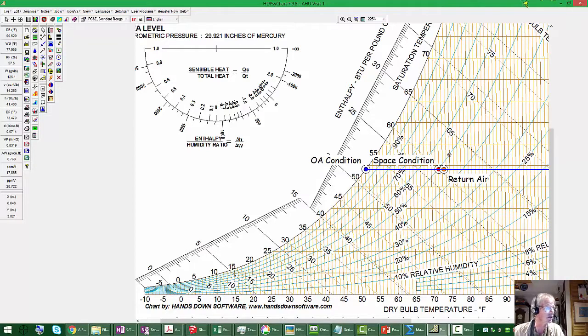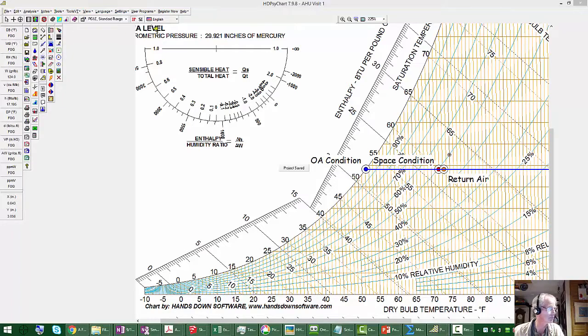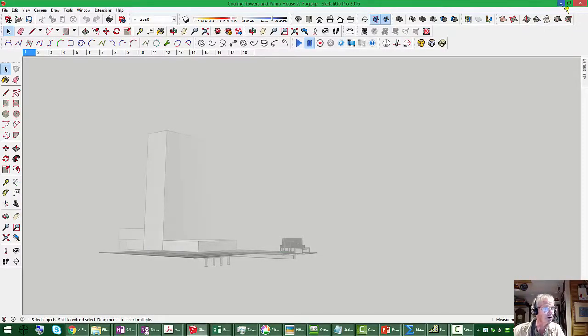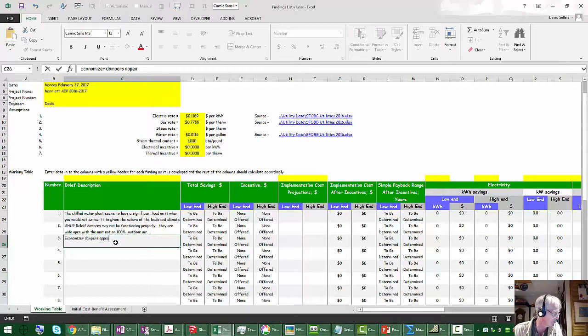So we've got another finding for our finding list, right? I'm going to save this so you can have a copy of it. Basically, it appears that the Economizer Interlock isn't working. Economizer dampers appear to be stuck on minimum outdoor air when they should actually be allowing 100% outdoor air, assuming an integrated economizer. Okay, if it was a non-integrated economizer, it might actually do that, but then that would sort of say, well, there's an opportunity anyway. And if you aren't familiar with the difference between an integrated and a non-integrated economizer, we'll eventually get to that, but Brian may have already talked about that.